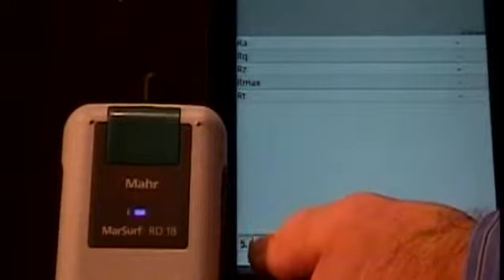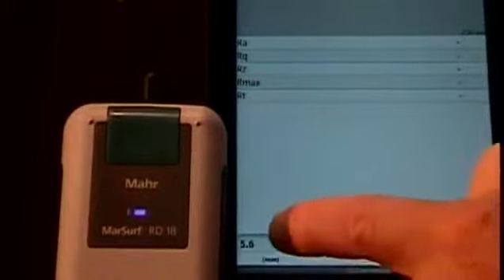As I'm talking here, it's taking the scan, and it's drawing me a little trace. Oops, move this down a little bit. It's drawing me a little trace, capturing my data across the screen. Now, in the lower left corner, you see a 5.6 there. That is the travel distance for the probe. I can select any travel distance I want there, up to the travel length of the skid on the RD18, which I believe is 17.5 millimeters. I have it selected for 5.6 just to keep the scan short here.